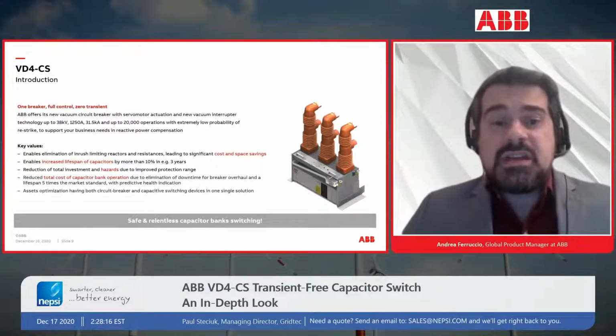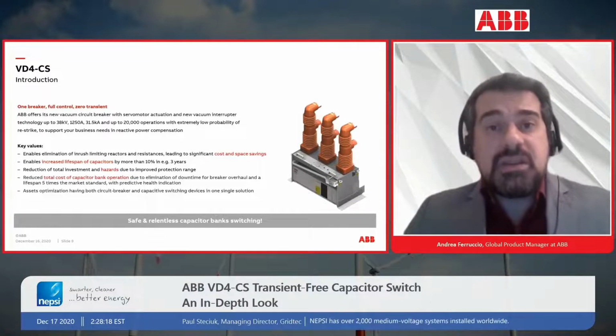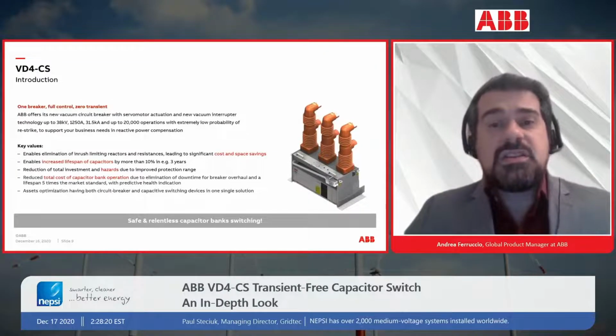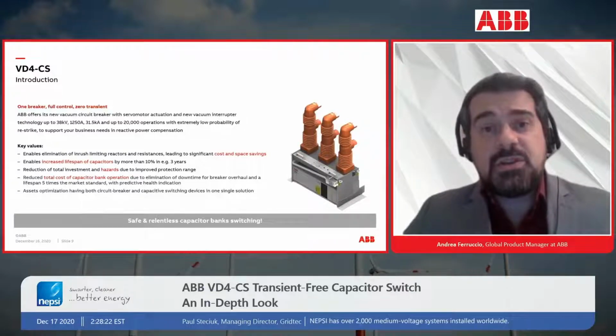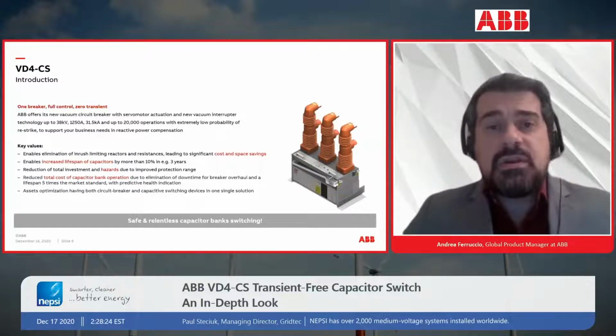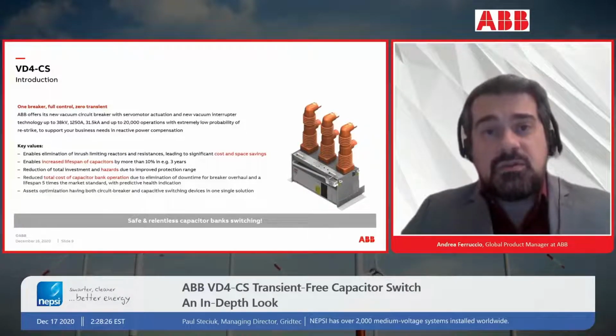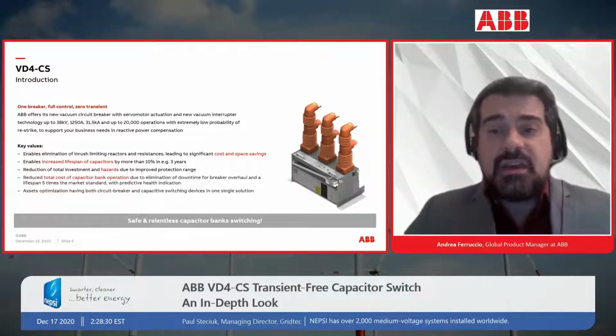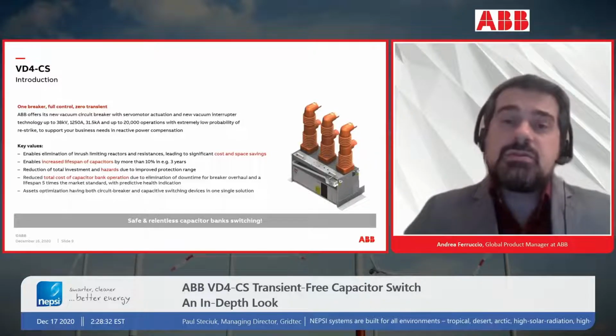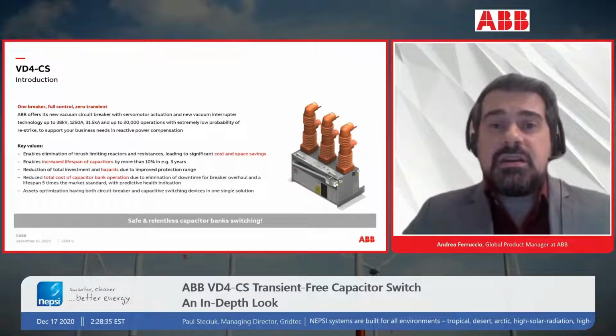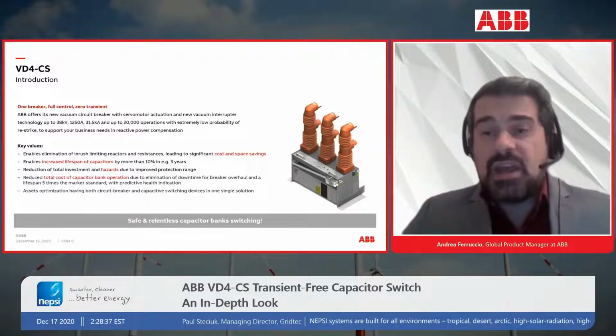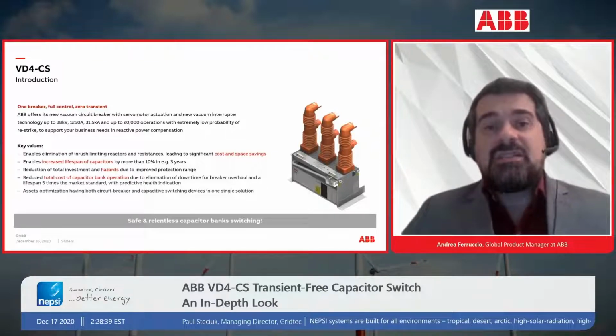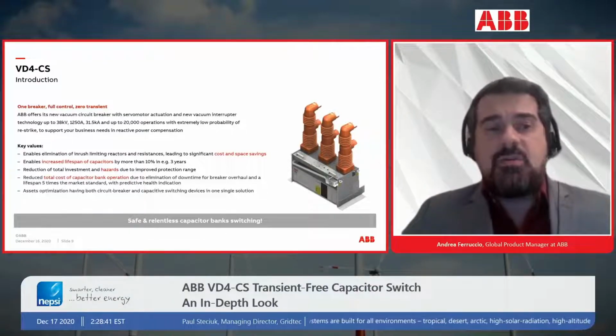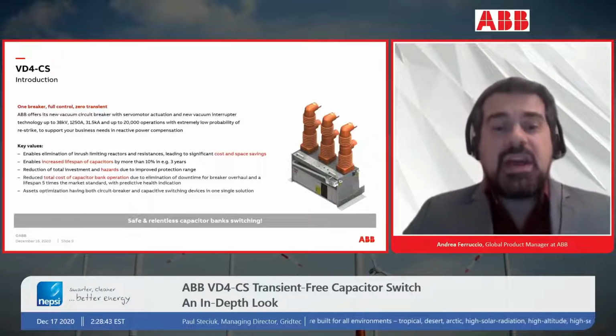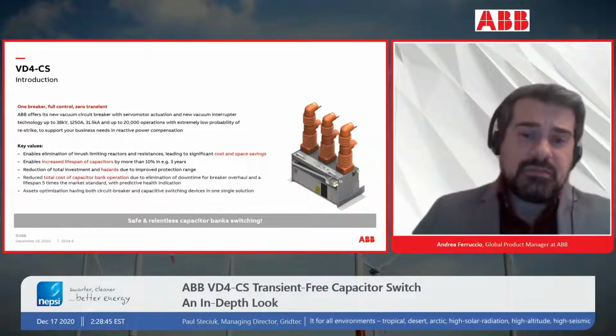Increased lifespan, as I said, we estimate up to 10%. Cost and space saving, thanks to the elimination of all those components able to protect so far and to limit the inrush currents. Thanks to the synchronization, thanks to this new product, we can eliminate inrush, we can eliminate noise, we can have finally an extremely low probability of restrike, with an improved protection range.